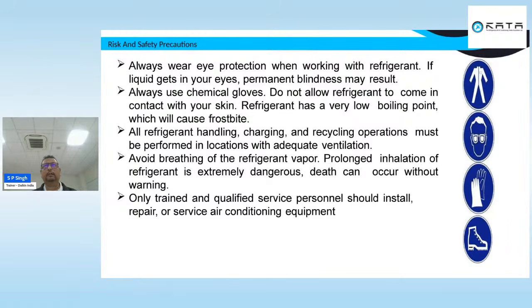Because outside ambient air will enter into your closed system, since it is a vacuum, and when it enters at positive temperature, that means moisture is also there, and suddenly moisture and dust particles will enter the system. The compressor cannot compress properly, and when it tries to compress, it will create high pressure or high temperature.